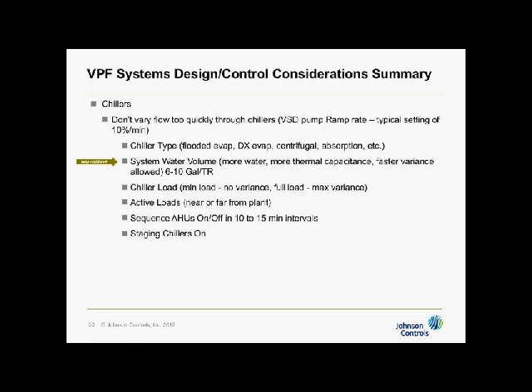Another way that I like to explain this particular phenomenon is when a gallon of water leaves the chiller and goes out to the system, breaks up and goes around to everything, and then reassembles in the return and returns back to the chiller, the amount of time that takes to leave the chiller and return, the longer it is, the faster the chiller can handle the rate of change. Okay?